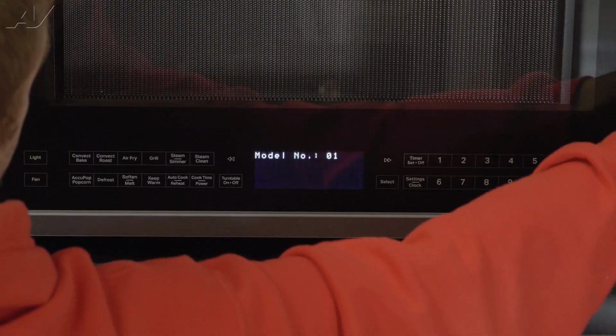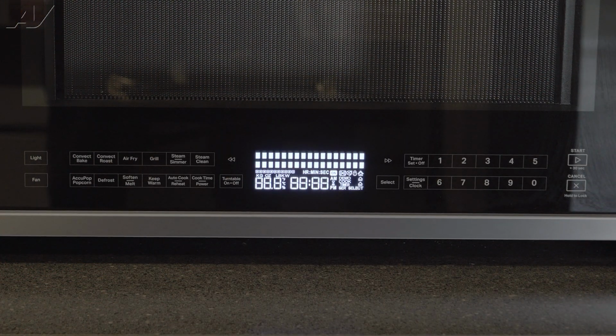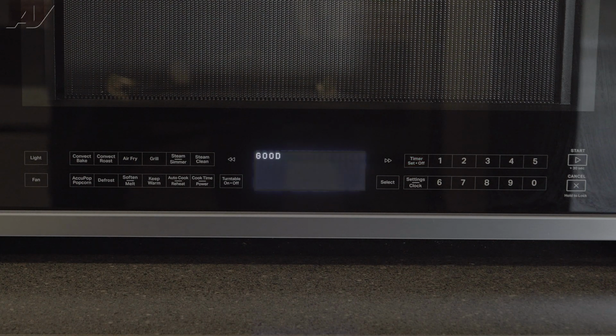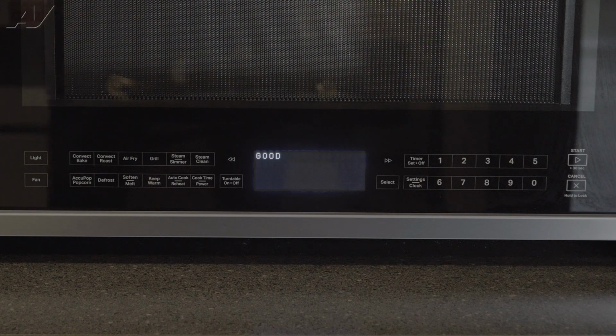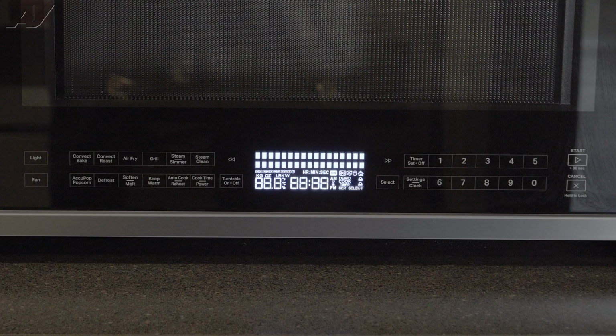So let's say you've gotten to the end of the error codes now. Open and close the door, then hit the timer button. The timer button is going to erase all the old service history. Whenever you go through the error codes and replace the component, make sure you erase those error codes so no other technician in the future gets confused. Once you hit that, it's going to show 'good' on the screen, indicating that all the error codes have been erased.